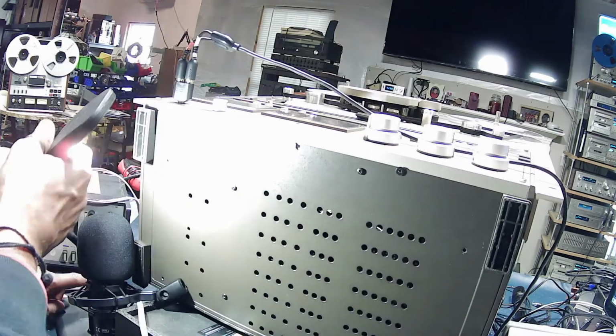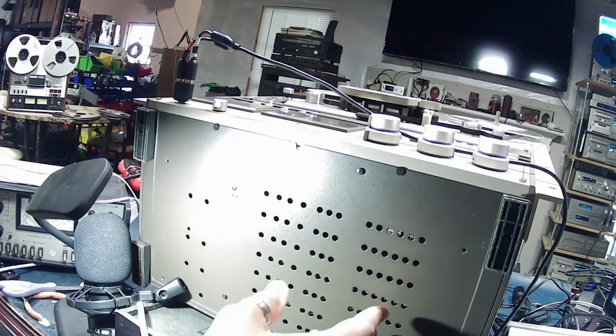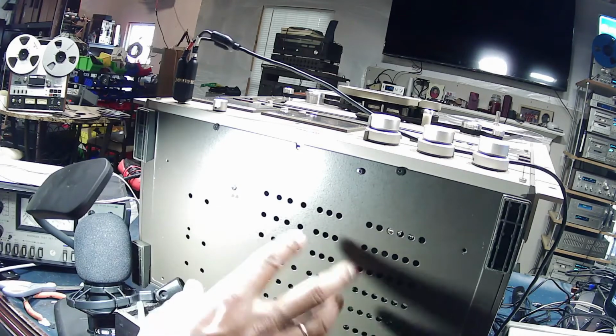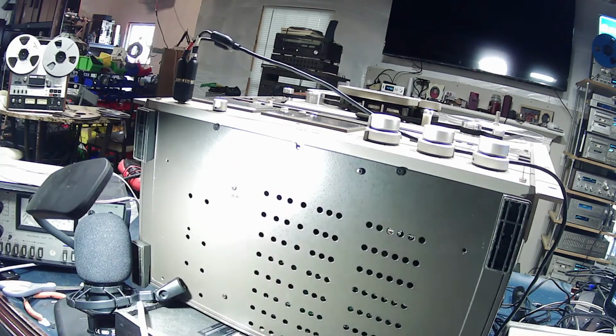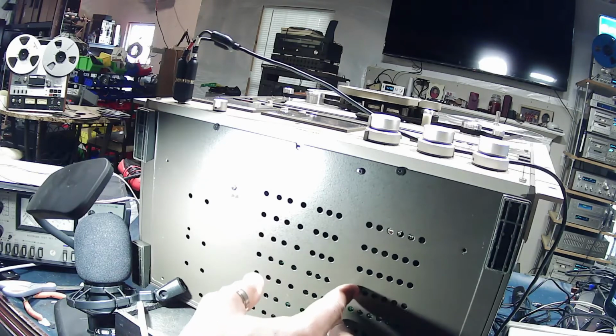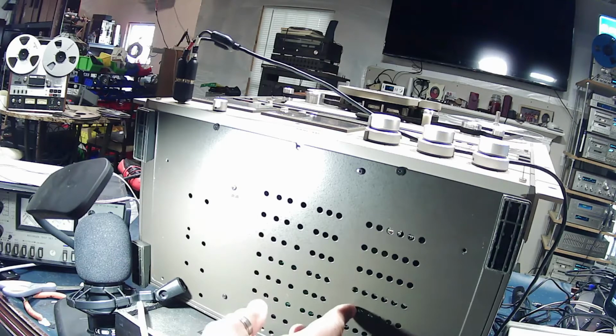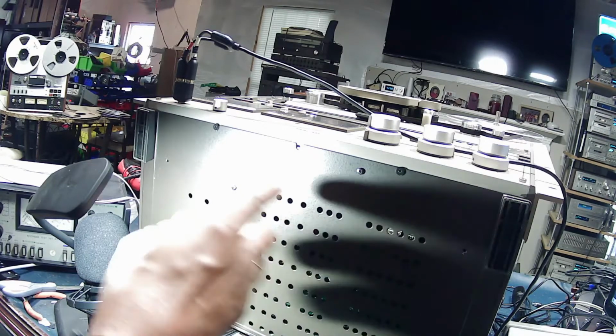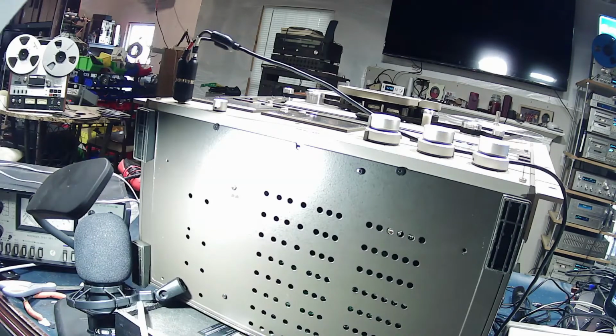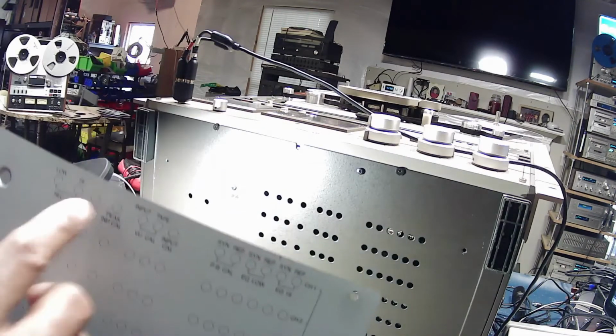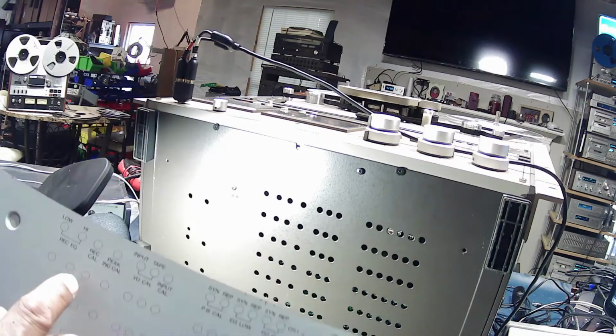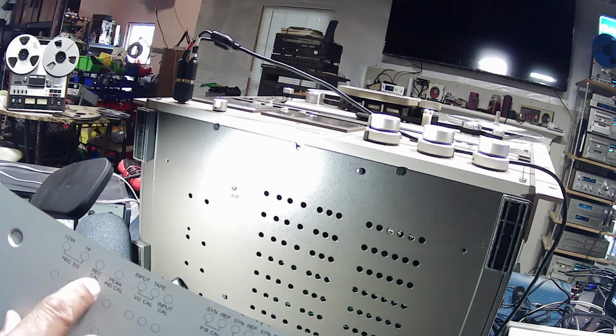On this Tascam 42, most of the potentiometers are located on these 2 rows. On this Tascam 42, the frame is the same as on a Tascam 48, and then all 8 channels would be located behind these slots. For the Tascam 42, they're only using 2 of those slots, and they're located right here for channel 1 and here for channel 2, the left and the right channels. And this area is normally covered with a bottom cover, but when you remove that cover, beneath it, it tells you what all the adjustment points are for. Like this is for record equalization, record calibration, and so on.